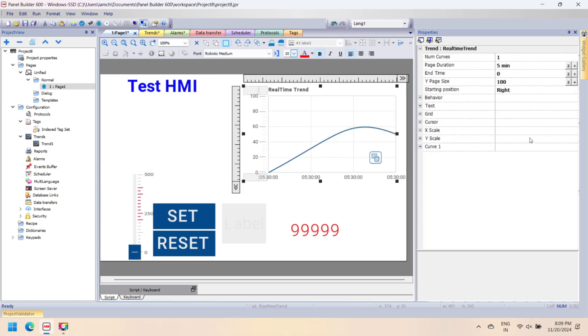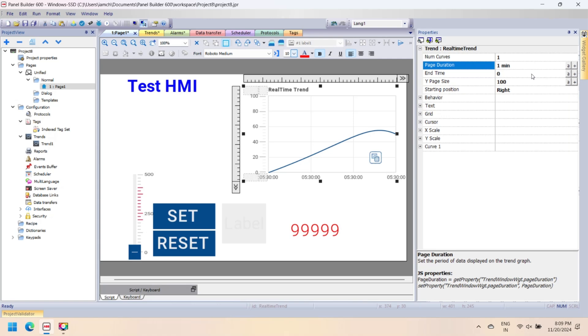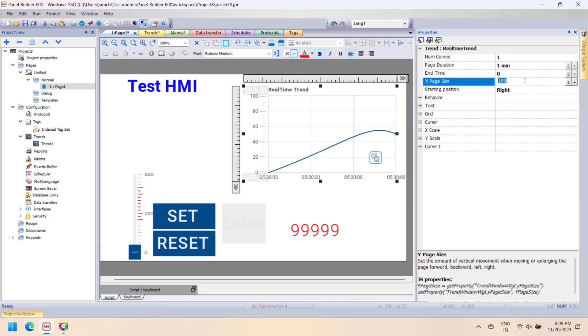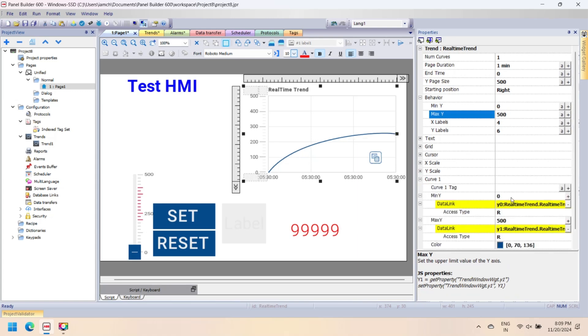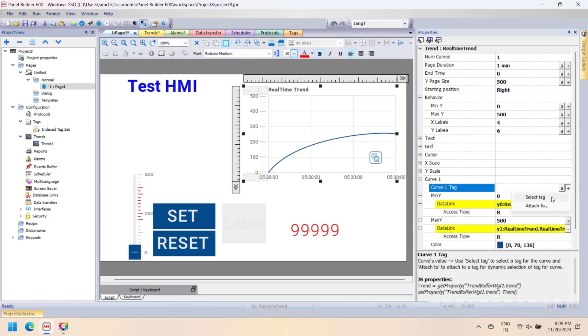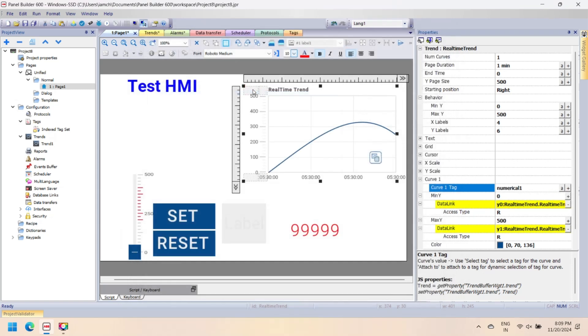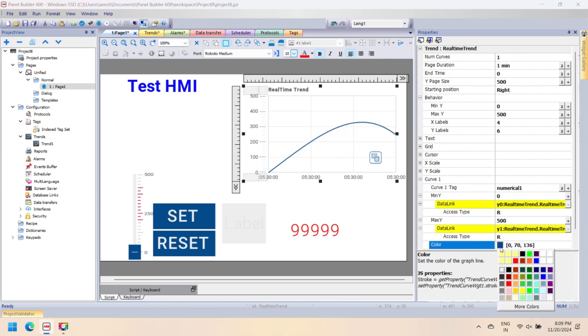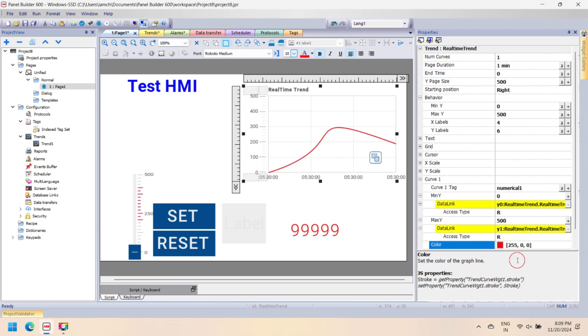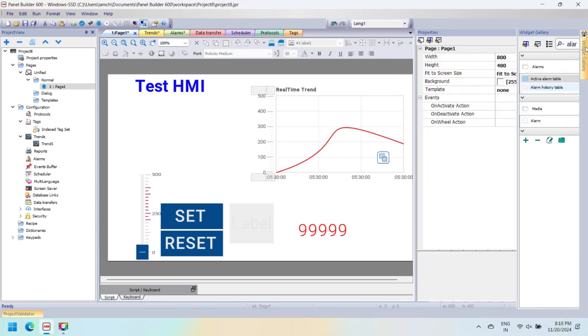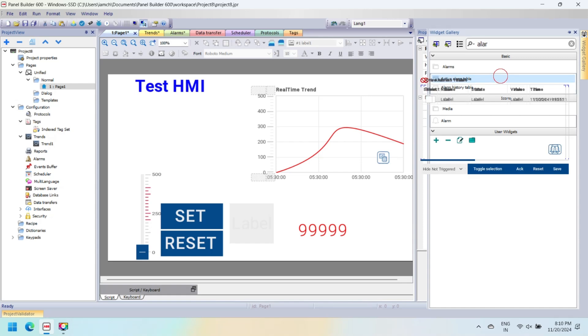Enter the curve number to display in the trend. If you want two trend curves, then enter two. Set page duration and time window to show. Curve property is an important property for trend. In this property, if you set two number of curves, then Curve 1 and Curve 2 are available. This property is used to set the tag and display format of the curve. In tag, select the tag to draw a curve. Set maximum and minimum axis of X and Y. Set the display color of your tag.